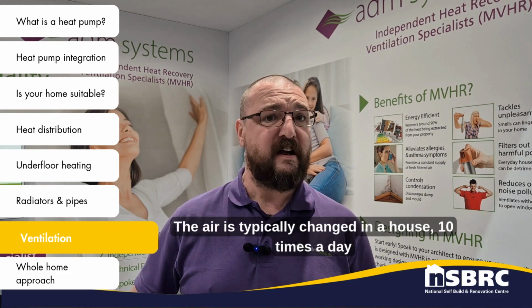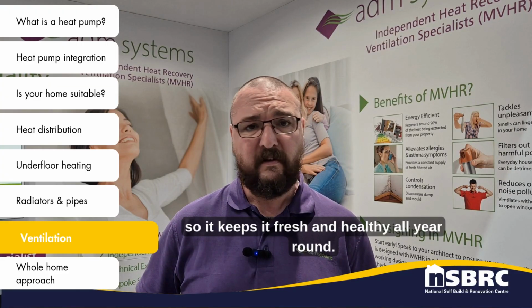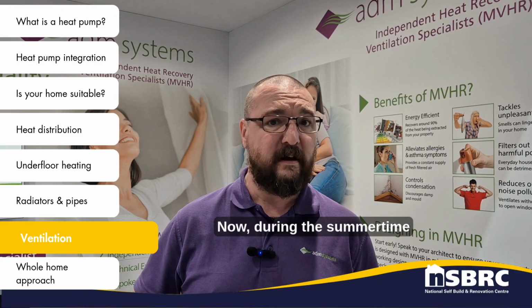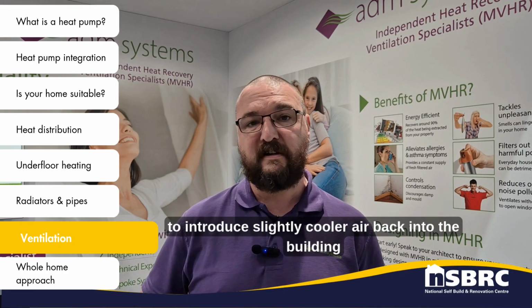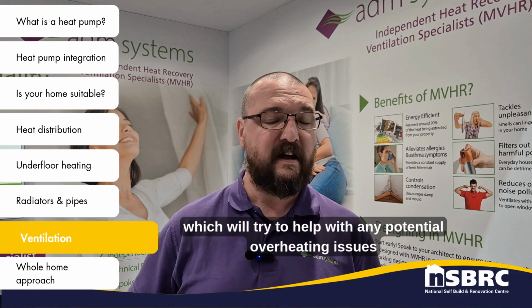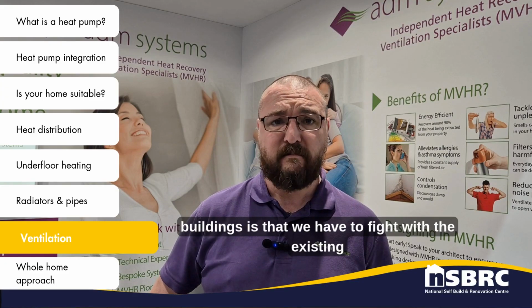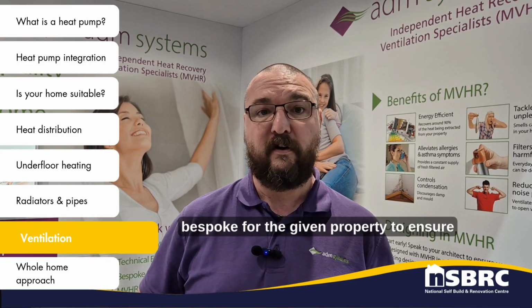The air is typically changed in the house 10 times a day, so it keeps it fresh and healthy all year round. Now, during the summertime, heat recovery is not normally required. The summer bypass on the units should kick in to introduce slightly cooler air back into the building, which will try to help with any potential overheating issues. The main crux that we have with MVHR systems going into renovations and existing buildings is that we have to fight with the existing structure of the building, which could be solid joists, steels, pipework and other obstacles. So it's very important that the system is designed bespoke for the given property to ensure both compliance of the system and also to guarantee any manufacturer's warranties.